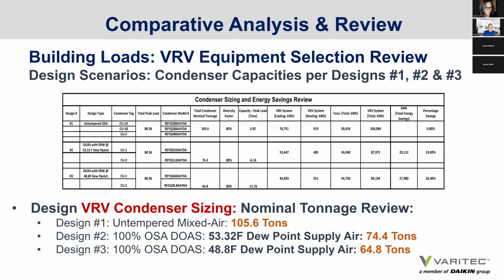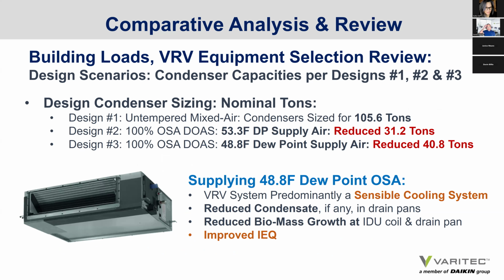You provide even deeper dew point control off the DOAS by increasing the size. We have a little bit more reduction in overall tonnage, and that's because your enthalpy wheel increases with the higher condenser size to provide the lower supply air condition off the cooling coil. So, if we look at it objectively, in this design scenario, you have an actual reduction of 31.2 tons by using a decoupled 100% outside air unit with 55 degrees off the coil or 53 degree dew point, and you reduce the overall nominal tonnage by 40 tons by providing 48.8 degree dew point as opposed to an untempered design.